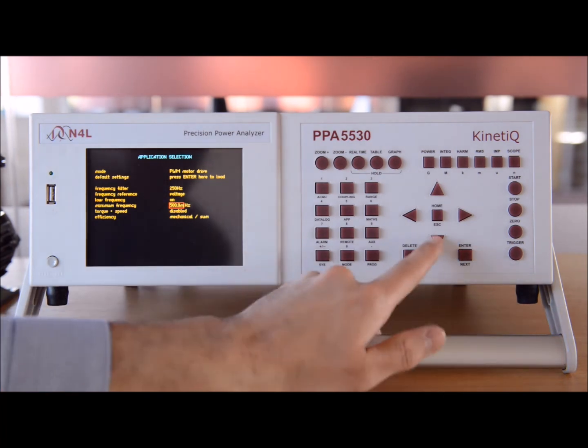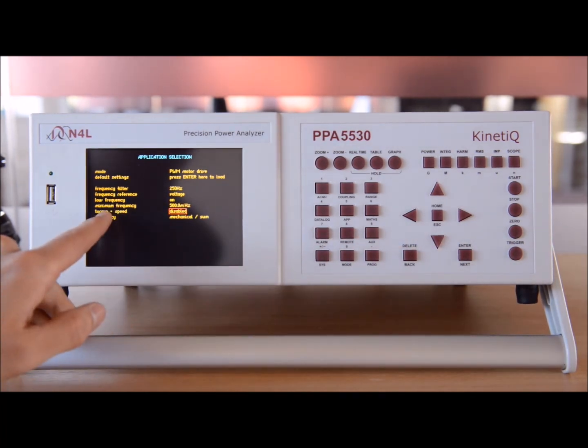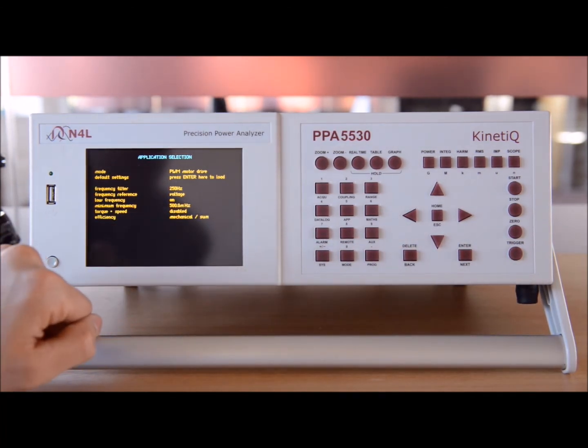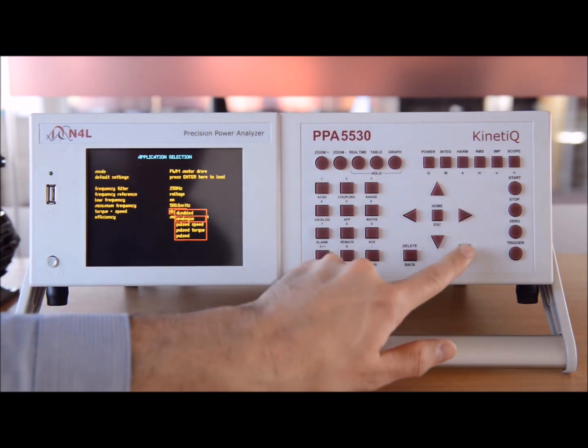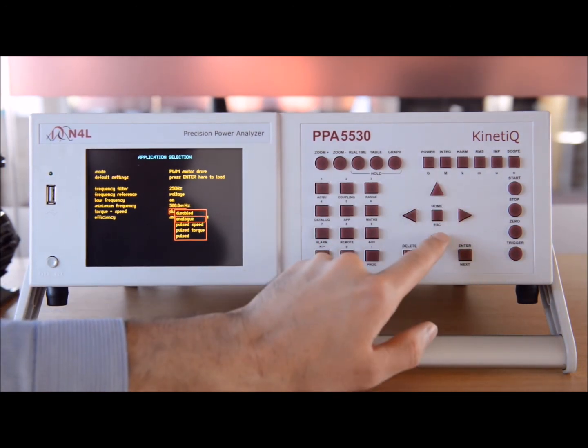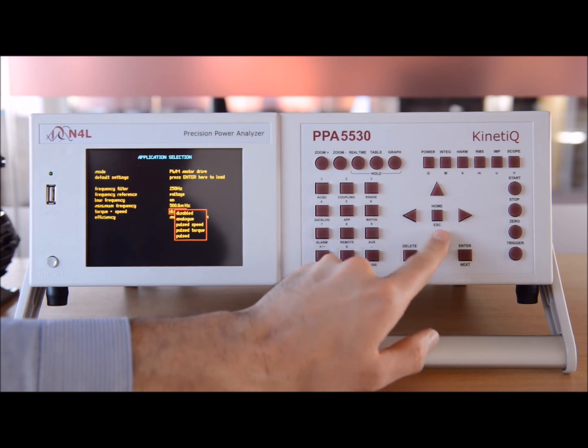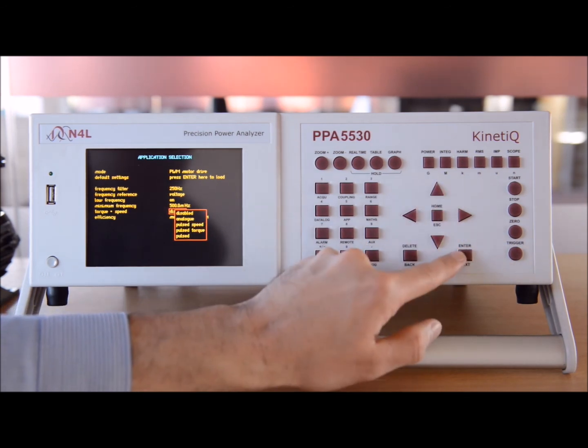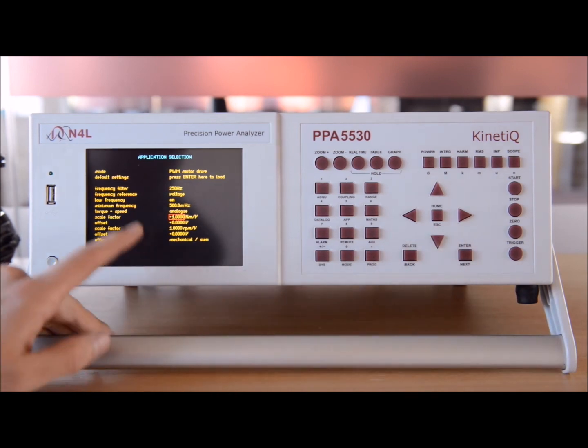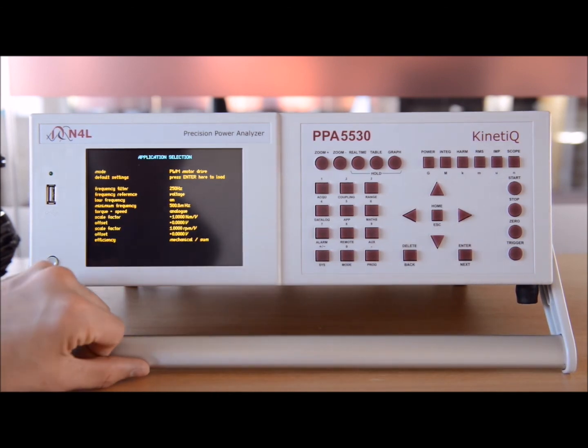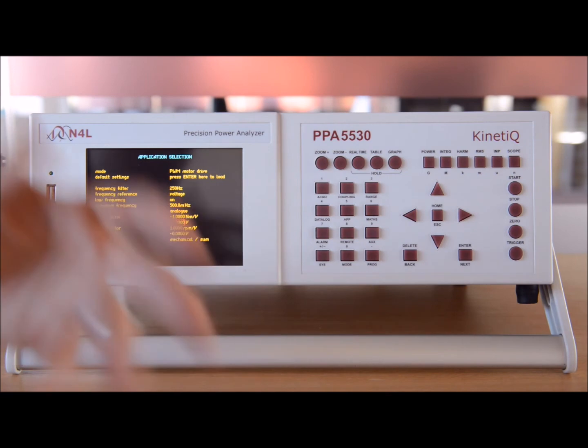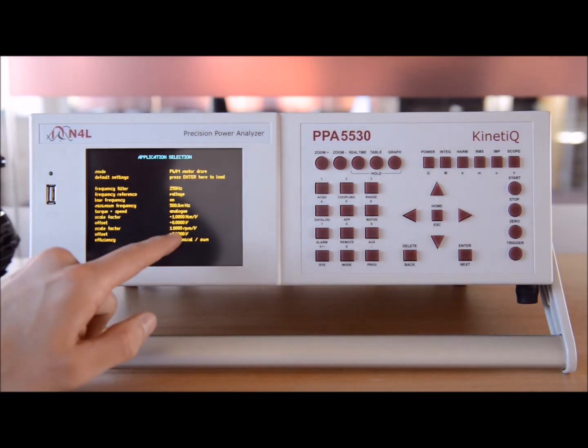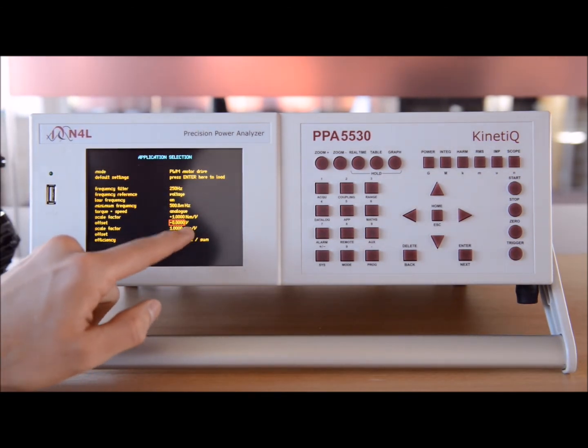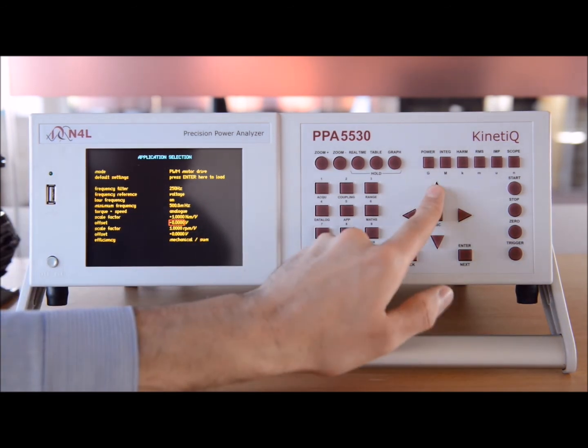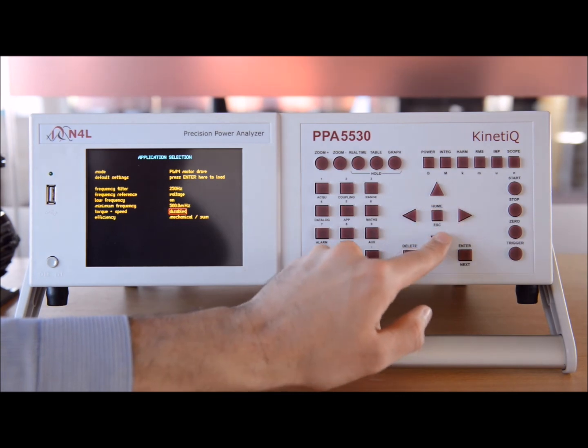So we need to talk about that. Now, the torque and speed inputs aren't going to be used today. If we did enable them, what we can choose is an analog version of both, a pulse torque, pulse speed, or pulsed versions of both. So if we had analog, for example, we can set how many Newton meters per volt we have there, an offset for the torque, and a speed per volt, so an RPM per volt, and an offset for the same. But let's turn that off.